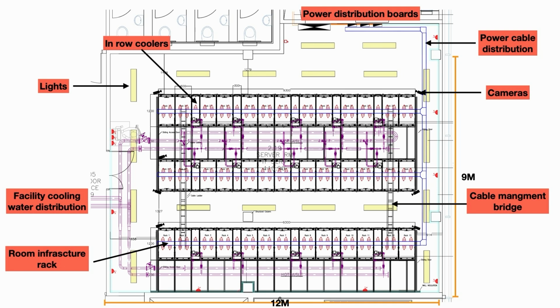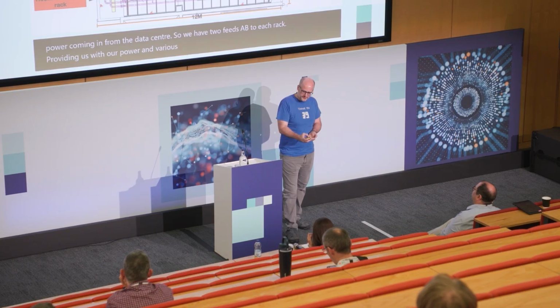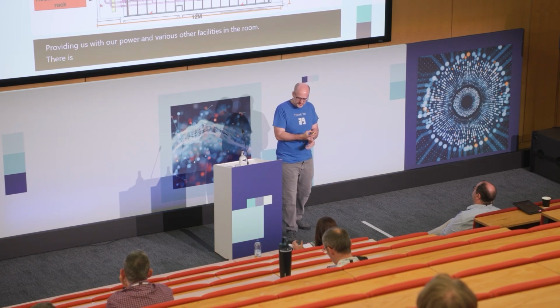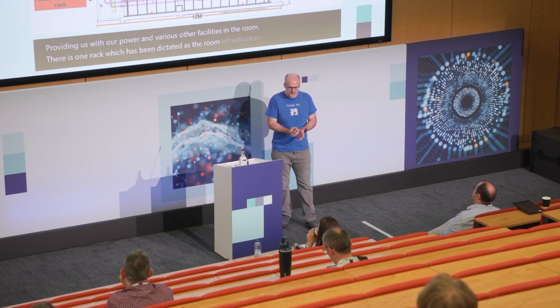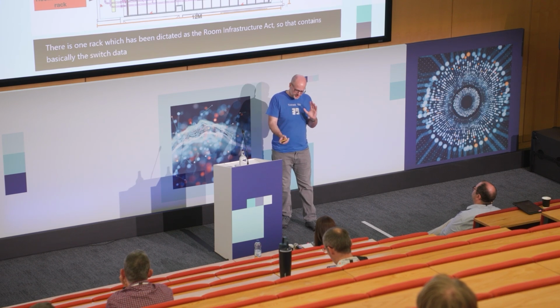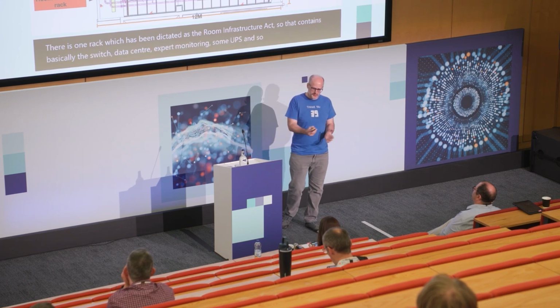Then just as a picture of the room, what it looks like, you can see the facility cooling water coming in from the left. At the top, it's above the door, and it goes above the hot aisles. And then on the far top right, you see the power coming in from the data center. We have 2 feeds, A and B, to each rack, providing us with our power and various other facilities in the room. There is 1 rack which has been dedicated as the room infrastructure rack. That contains the switch, Data Center Expert monitoring, some UPSs and so on for managing the room and the network in the room.